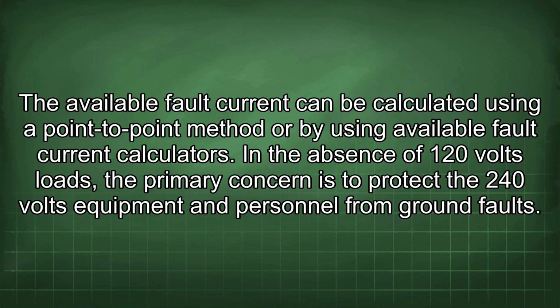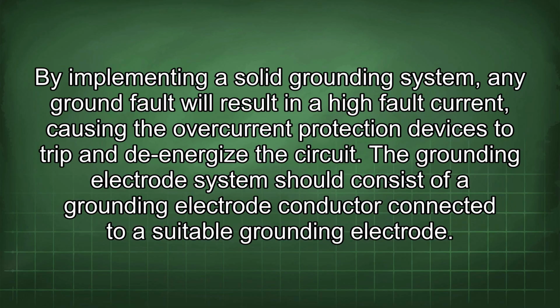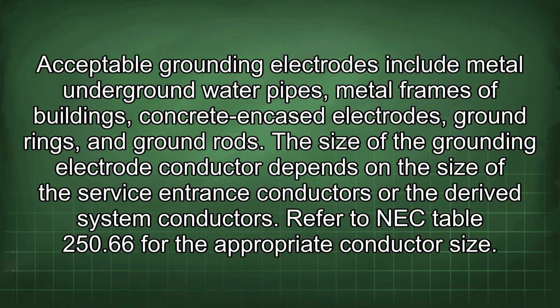In the absence of 120 volts loads, the primary concern is to protect the 240 volts equipment and personnel from ground faults. By implementing a solid grounding system, any ground fault will result in a high fault current, causing the overcurrent protection devices to trip and de-energize the circuit. The grounding electrode system should consist of a grounding electrode conductor connected to a suitable grounding electrode. Acceptable grounding electrodes include metal underground water pipes, metal frames of buildings, concrete encased electrodes, ground rings, and ground rods.